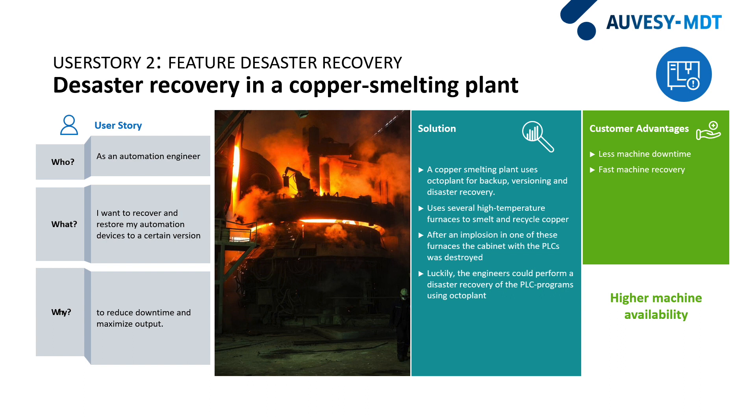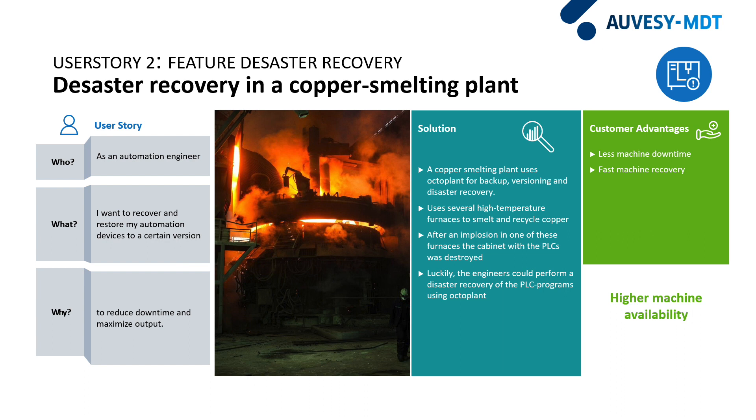It uses high temperature furnaces to smelt and recycle copper. What happened in the past is that an implosion occurred in one of these furnaces. This caused the liquid copper to leak out. The molten metal set fire to the electrical distribution panel, the cabinet, along with the PLC controllers. The PLC controllers were damaged afterwards. But fortunately, a backup of the PLC controller code had been made before with OctoPlant. Luckily, the engineers could perform a disaster recovery of the PLC programs using OctoPlant.